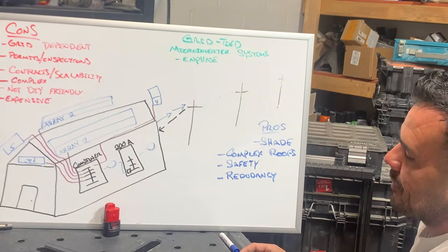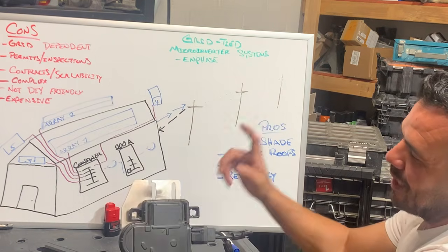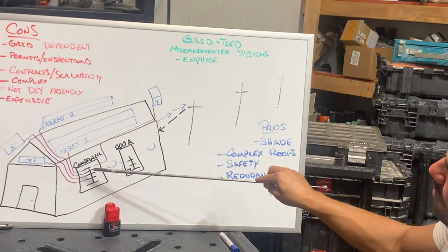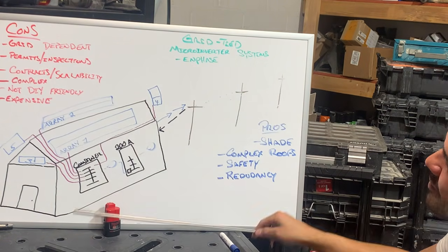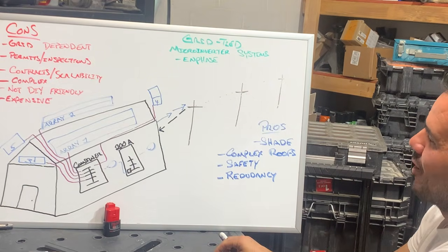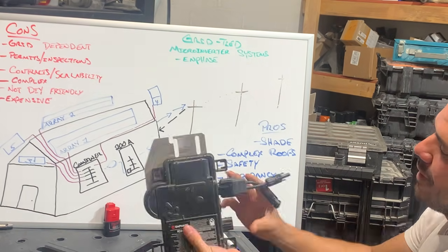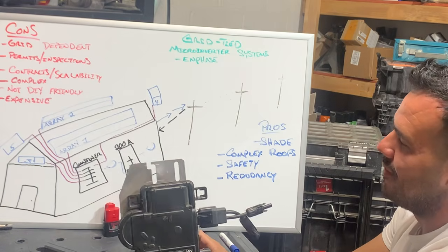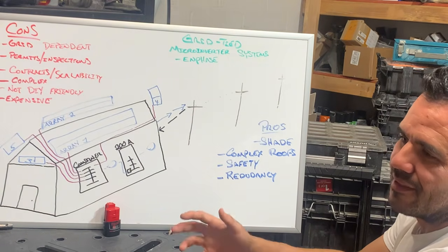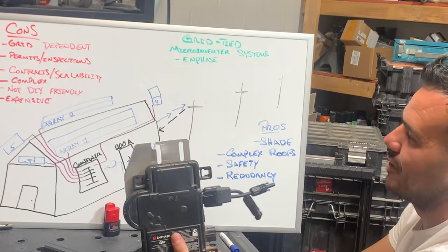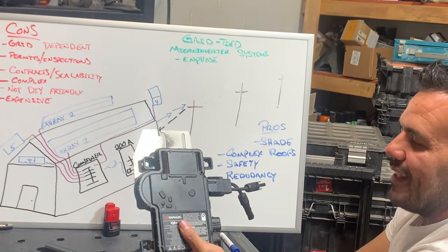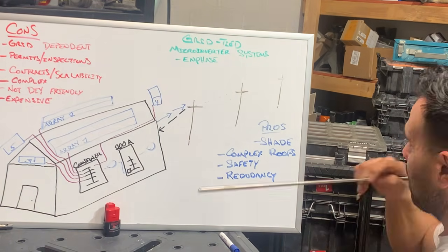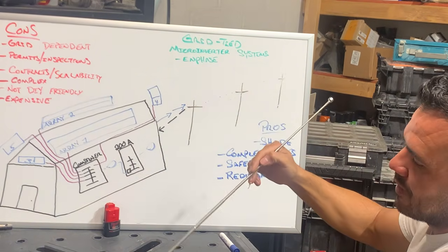The problem with these also becomes, because you have 15 of these, you also have 15 connections here, 15 more connections here, and so now you have a bunch of wires and connection points in the combiner box. Now there's a computer in the combiner box you've got to worry about. So many more connections and failure points in your solar system, where string inverters have less components, less pieces, less wiring. These get complex really quick, and there's a lot of connections and points that can fail. So that's one of the cons, a lot of connection points.